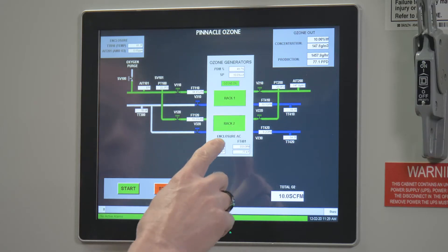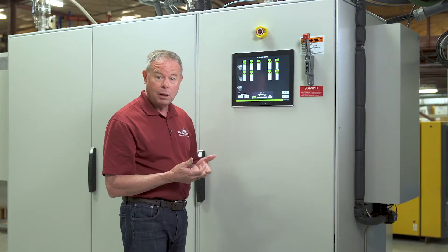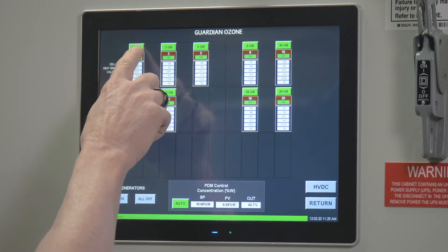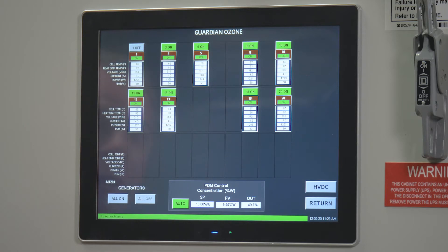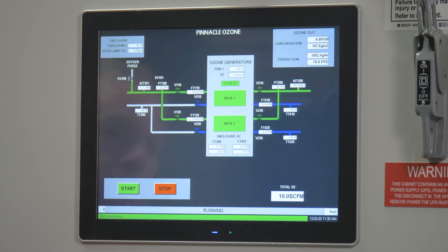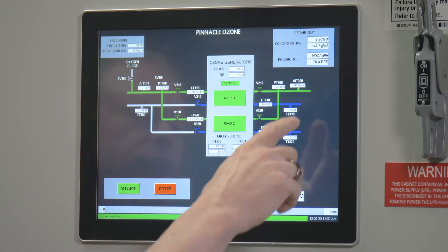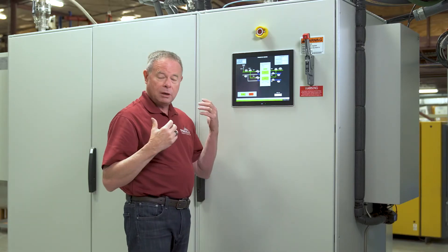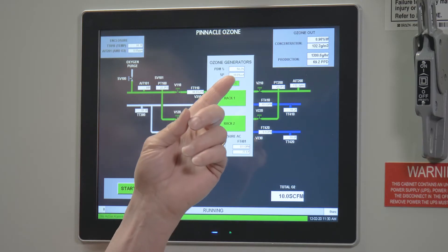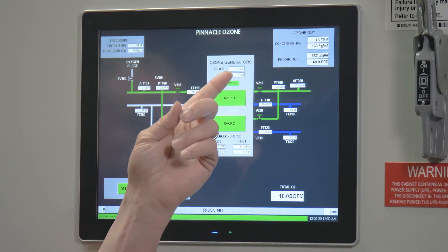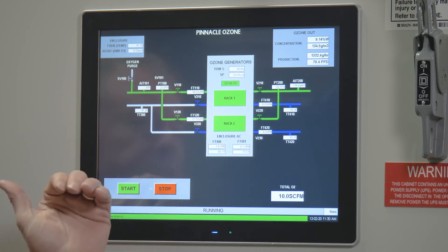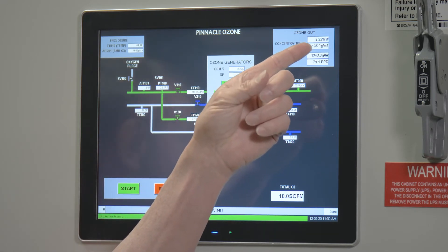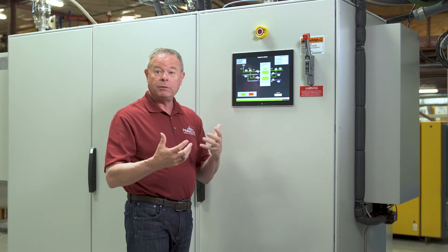I'm going to simulate a failure by turning off one of the quad blocks. To do that, I simply press that. Now the generator's turned off. And what you're going to see here is the concentration starting to drop. Our concentration is starting to drop — 9.93, 9.9. One generator is just passing oxygen gas through it. Concentration's falling, but the power is starting to ramp back up: 54, 55. And now you see the concentration starts to come back up. This system is recovering very quickly.